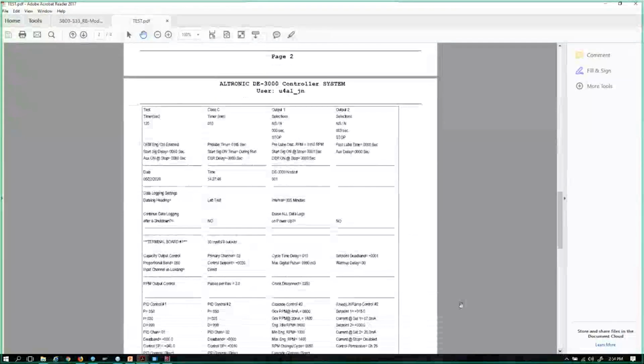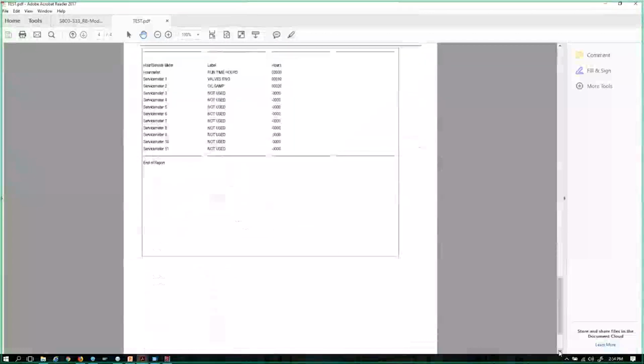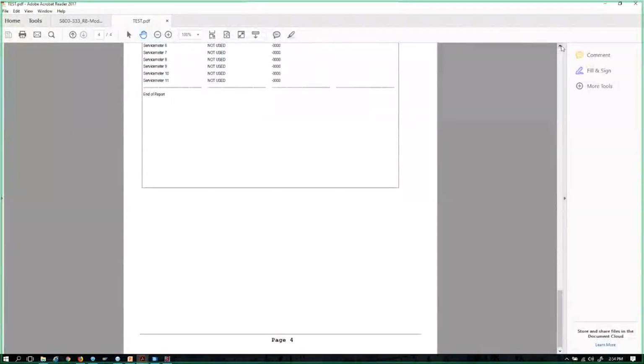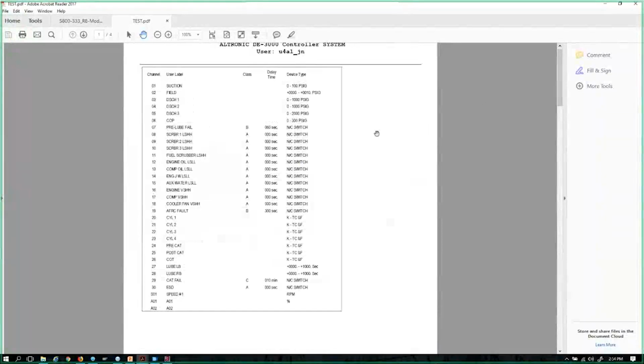Tells you a little bit about what's going on in the startup sequencing. Tells you information about your service hour meters and your hour meter. And there was something earlier, and the reason I wanted to show you this, when I started talking about normally open and normally closed. Here's a great example. Right here, we can see that channel 7 is, all these discrete channels are actually all configured as normally closed, but this is where the tech, if he or she saw one that said normally open, all of a sudden, if they're building the unit, wiring the unit, they know to wire this one a little bit different.